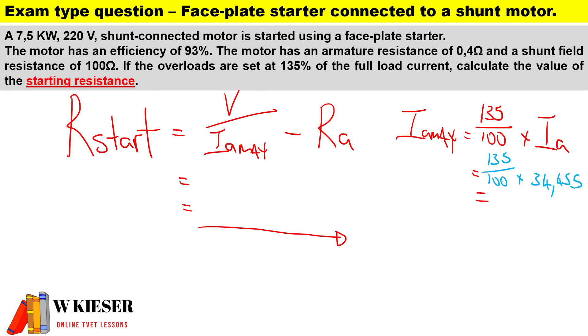Now we can actually go ahead and substitute. Our terminal voltage for our machine is 220V, the I_a_max of 46.514A, subtract our armature resistance of 0.4Ω. So therefore the resistors that are connected in series with the armature will be 4.33Ω.